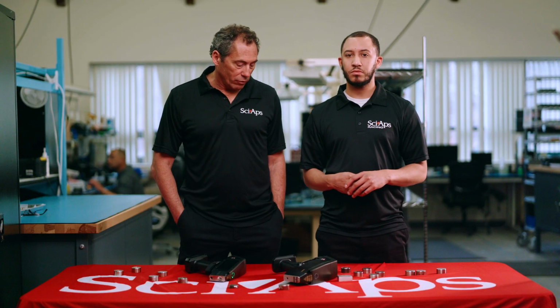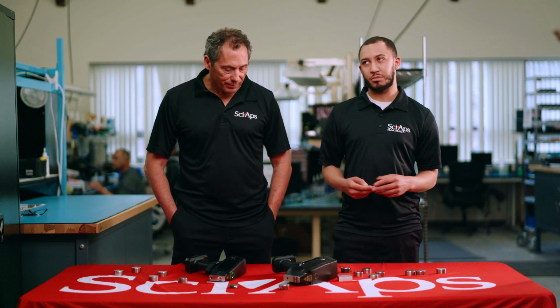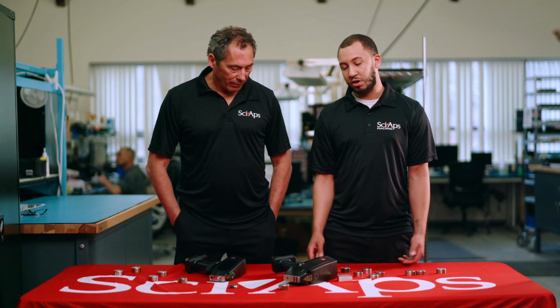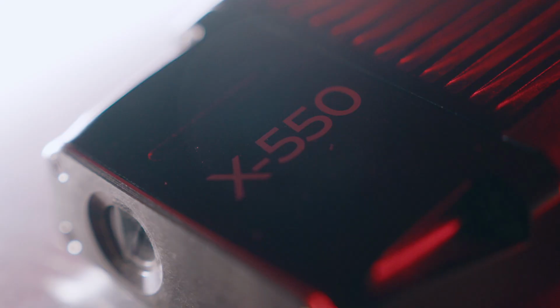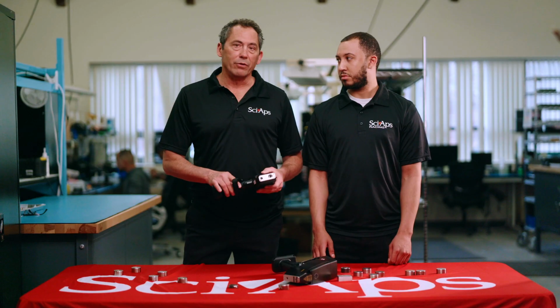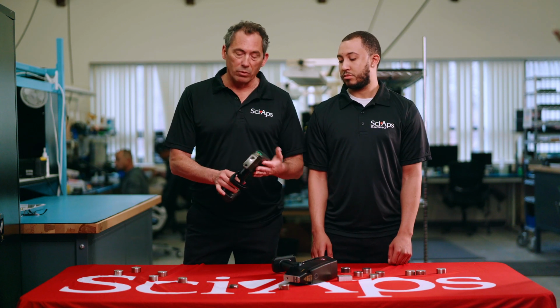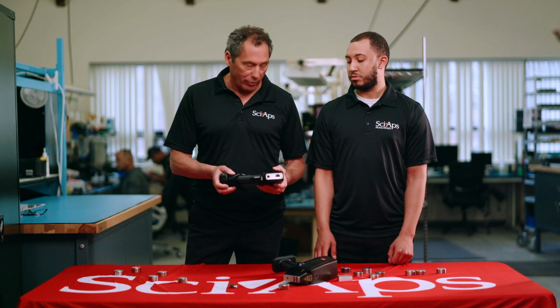Couple hours? Yeah. And if you have to fix the laser or do a realignment, then you have to recalibrate and everything. That could push up to days, depending on the unit and exactly what's wrong with the unit. In terms of the X-ray, I know if it's just an alloy unit, you pop in a new detector if that's broken or a new tube or whatever, you recalibrate it and it can be a pretty quick turnaround.